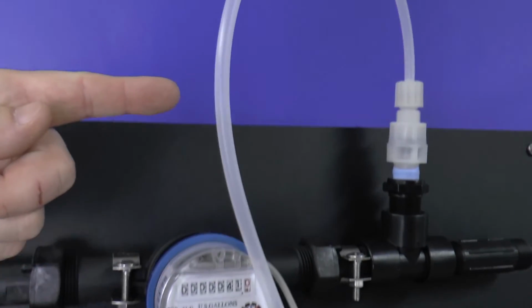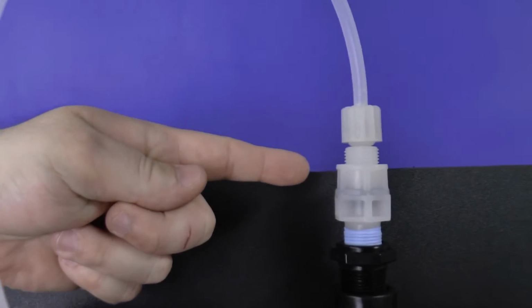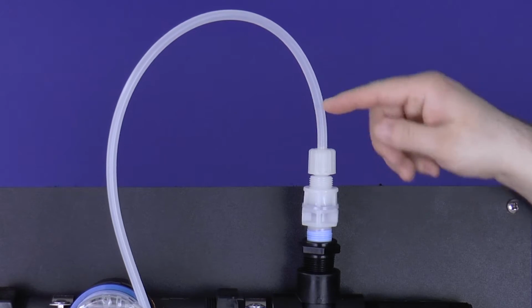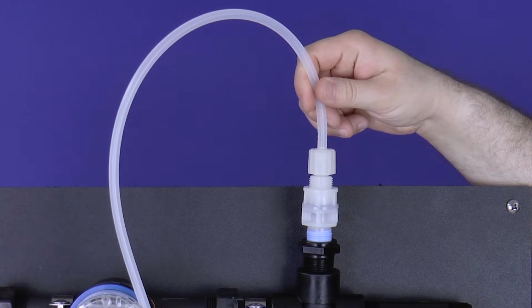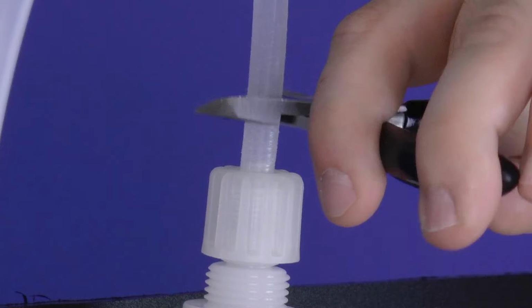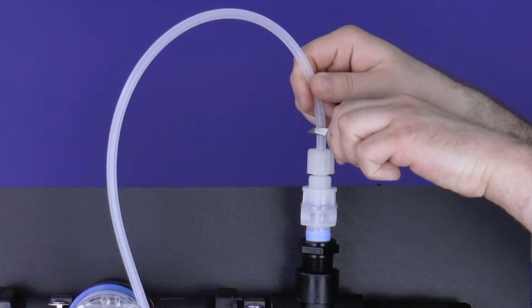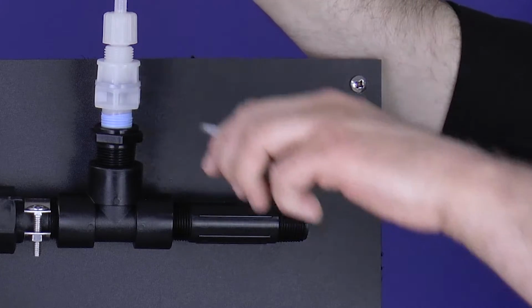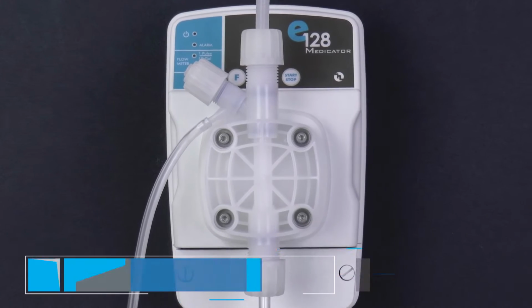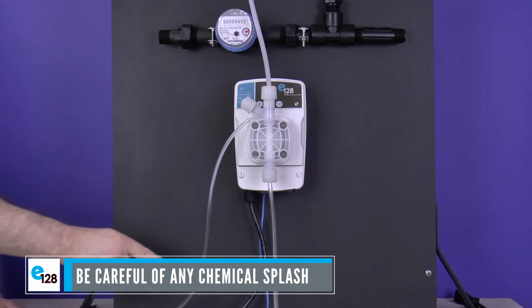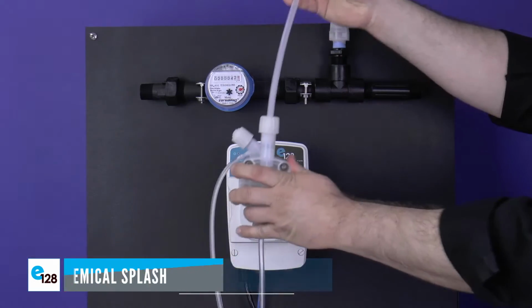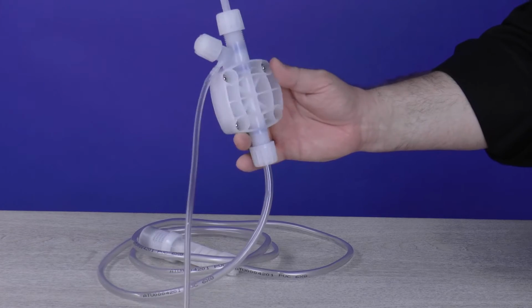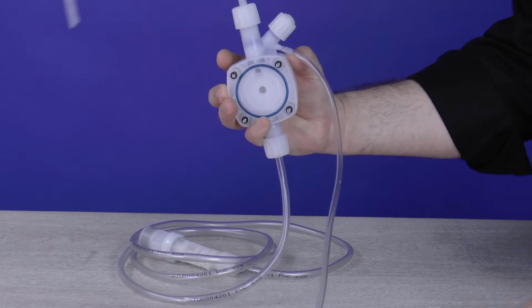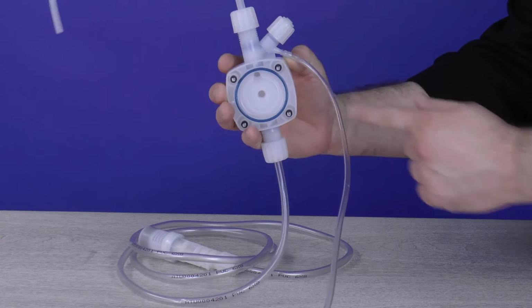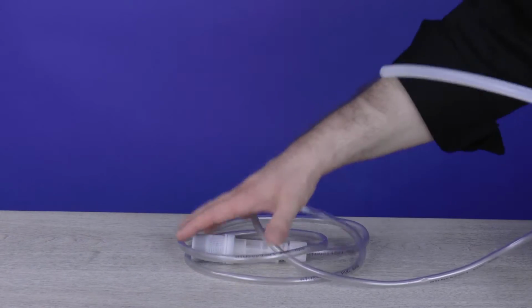Locate the used rigid discharge tubing connected to the old injection valve. Keep the tube upright to ensure no remaining chemical spills out. Use the diagonal pliers or cutters to cut the tube as close to the old injection valve as possible. Set the diagonal pliers down and use the same hand to remove the pump head along with the connected tubing and foot filter. They should all come off as one piece. Once removed, check the back side of the pump head to see if the blue O-ring is in the groove. If the O-ring is there, then discard the pump head along with the blue O-ring, connected tubing, and foot filter.